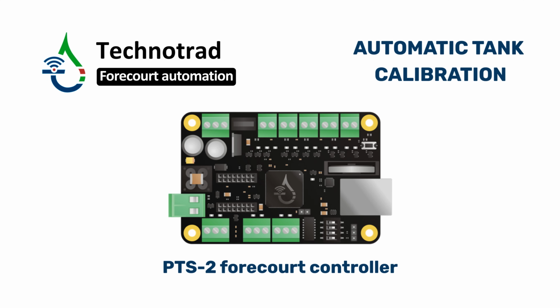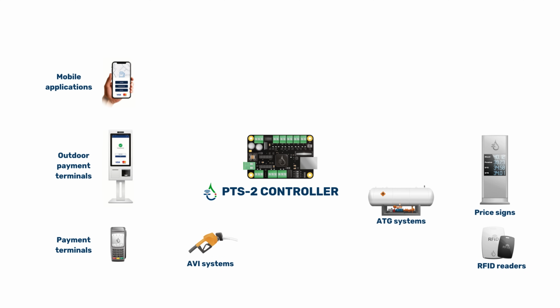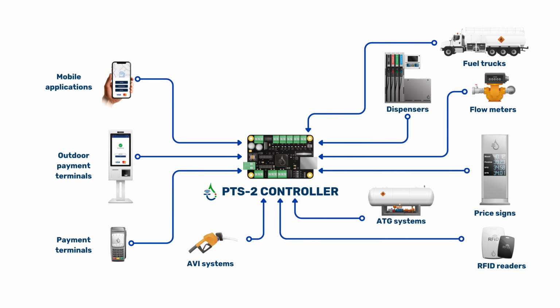The Technotrade company created the non-invasive automatic tank calibration procedure using the PTS2 forecourt controller to make the process easy and keep your tanks up to date with the correct calibration chart and without having to shut down the whole gas station. The PTS2 is a forecourt controller designed to regulate the filling station equipment, oil terminals, and fuel delivery trucks. It supports more than 200 brands of dispensers and ATG probes from various manufacturers.